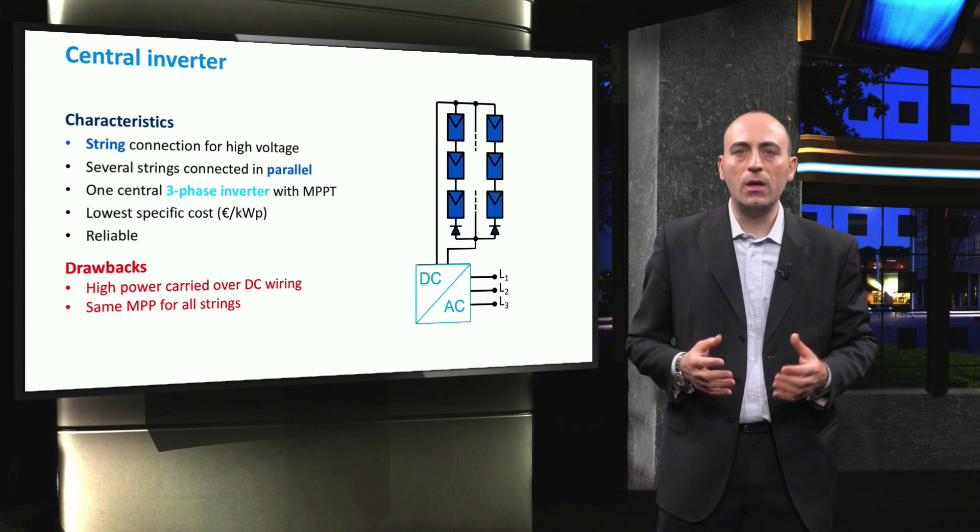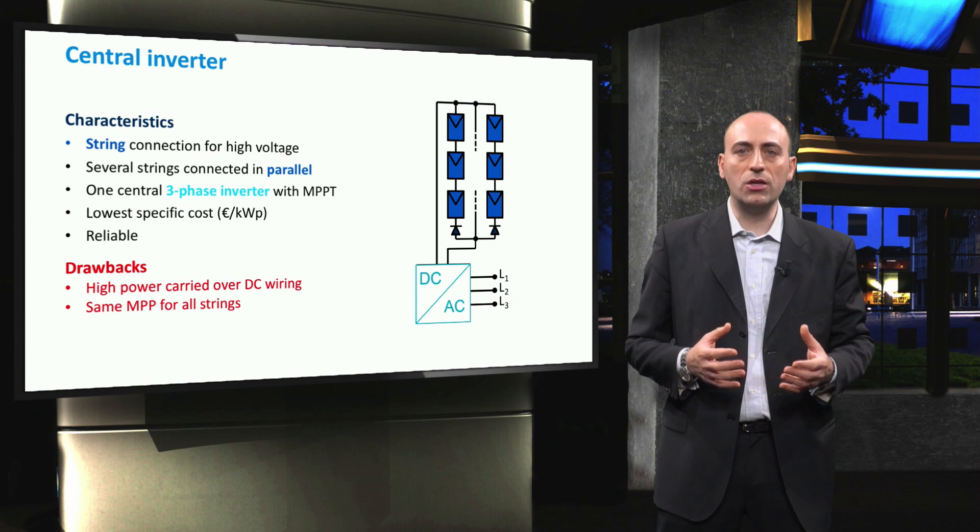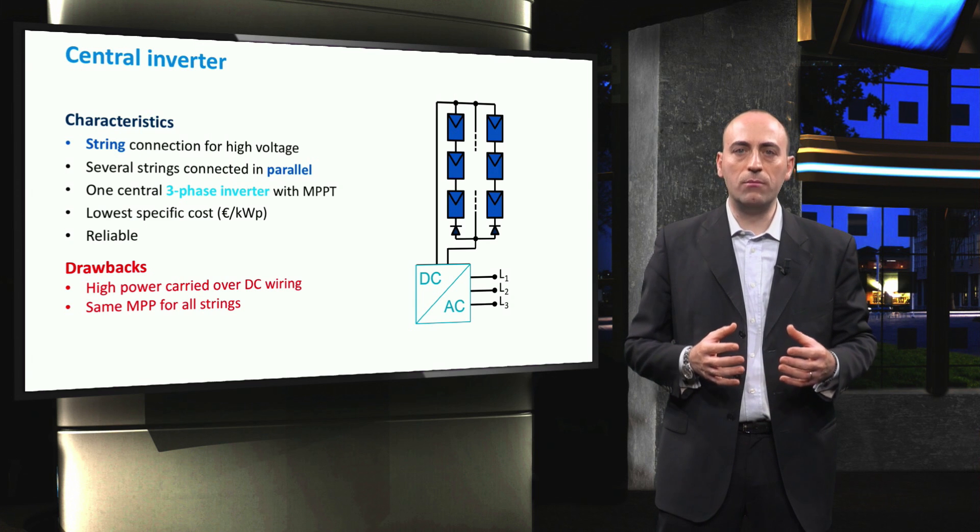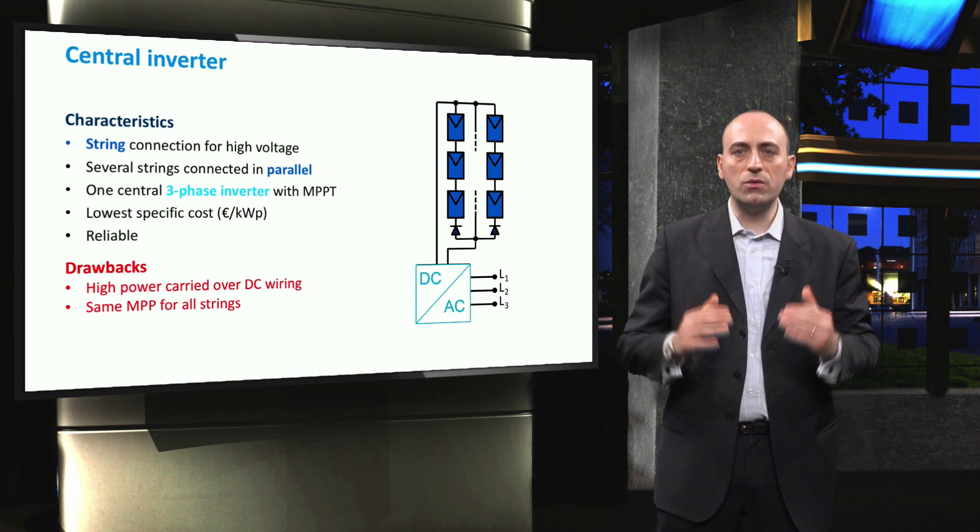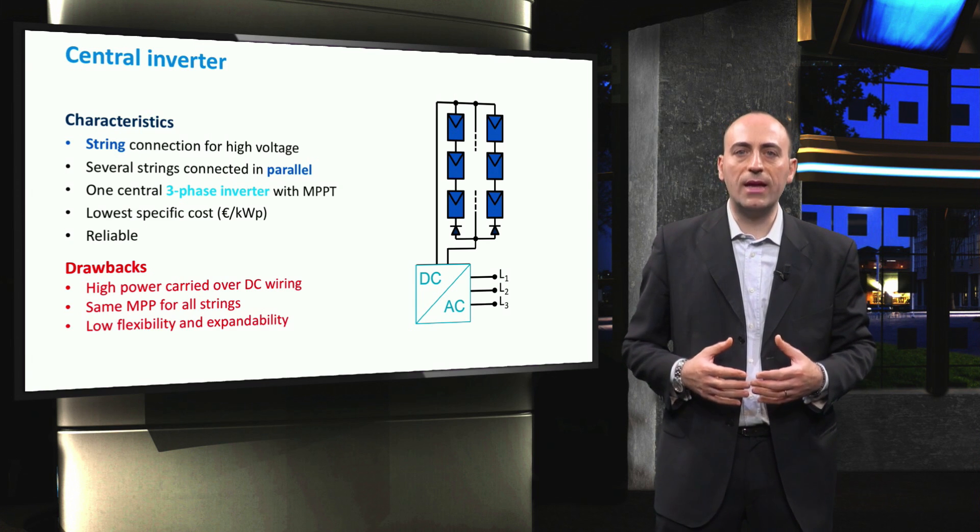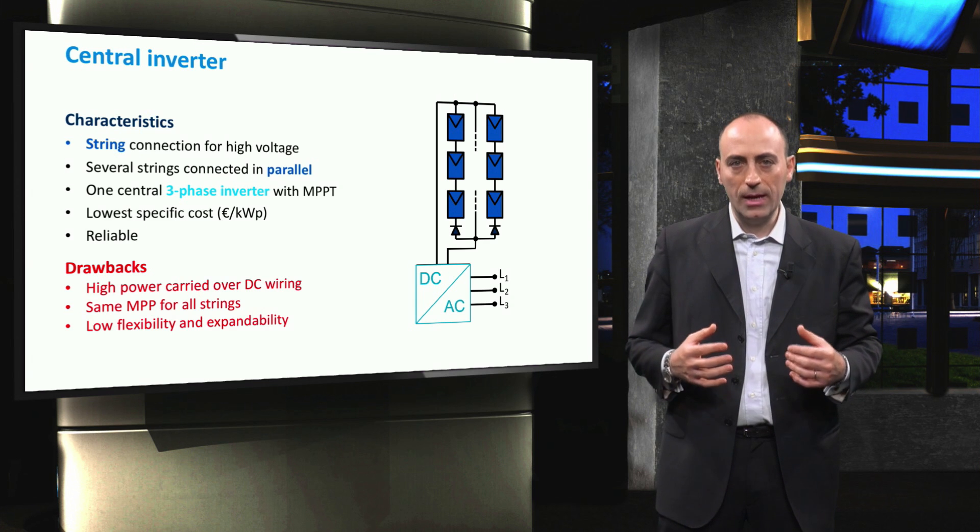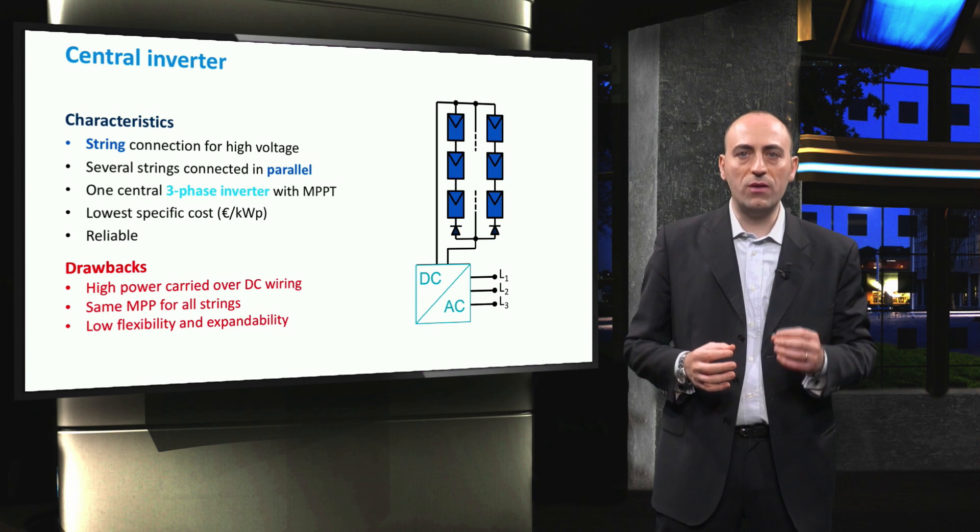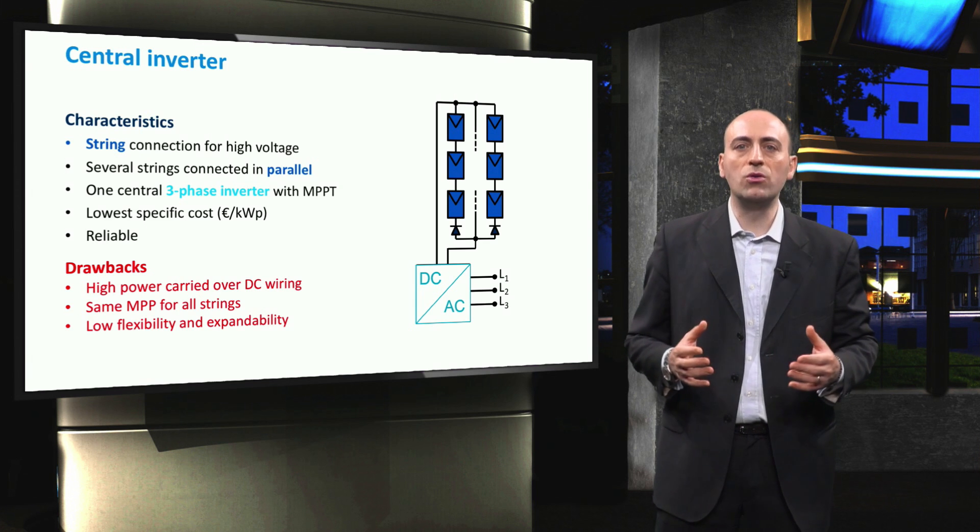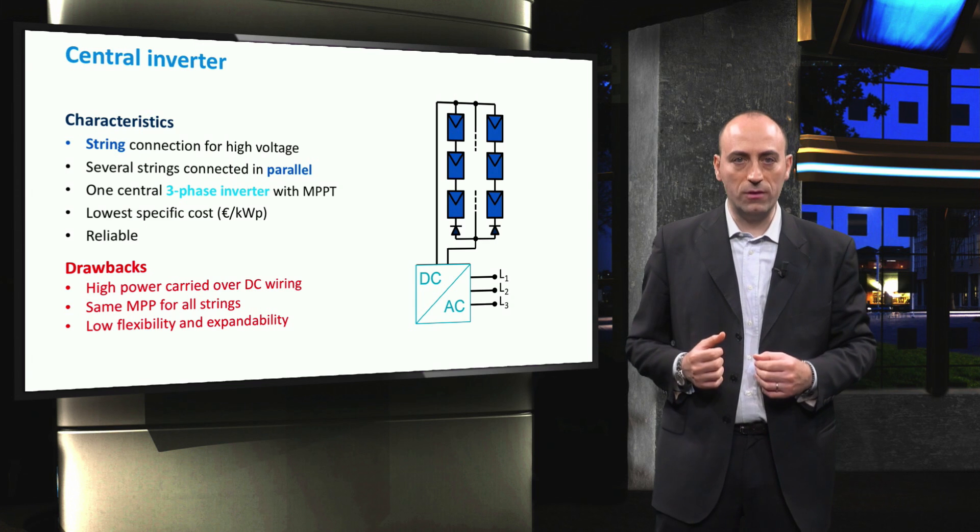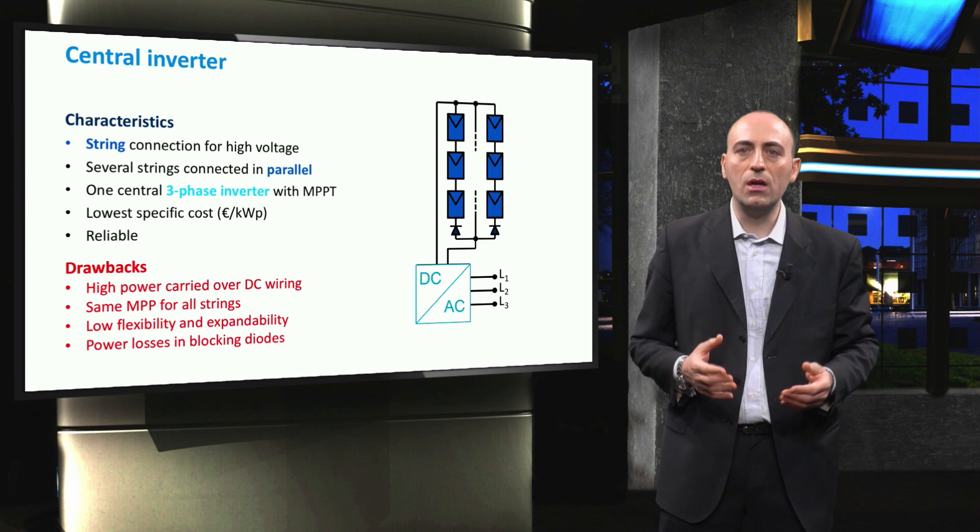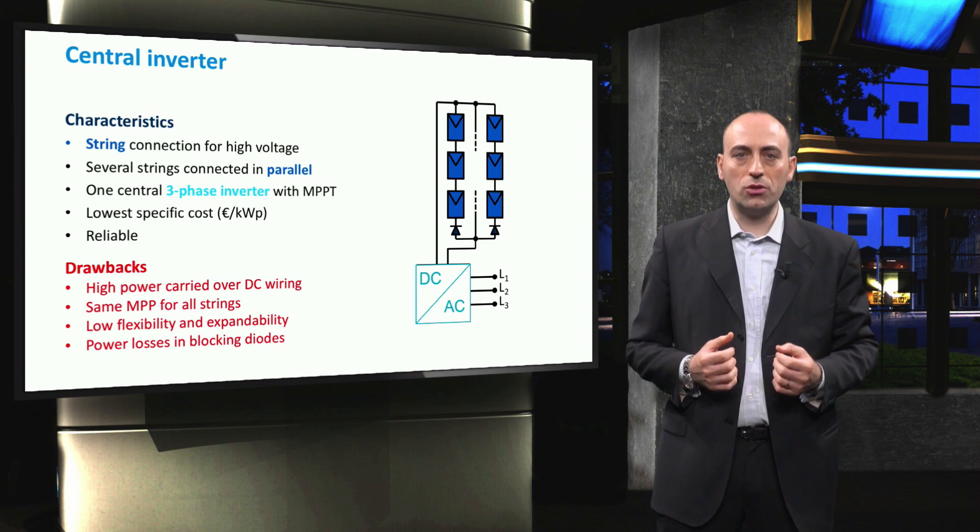Imagine, for example, a cloud casting its shadow on part of the installation for a couple of seconds. The result is a high imbalance in the power generated by the modules that causes mismatch losses and reduces the overall system output. A third drawback is the low flexibility and expandability of the system. As the central inverter is designed to work with a specific installed peak power, its maximum input power is limited, and so is the number of modules that the array can accommodate. Lastly, since we have to use blocking diodes in each string to prevent current circulation, then we have to consider also their additional power losses.